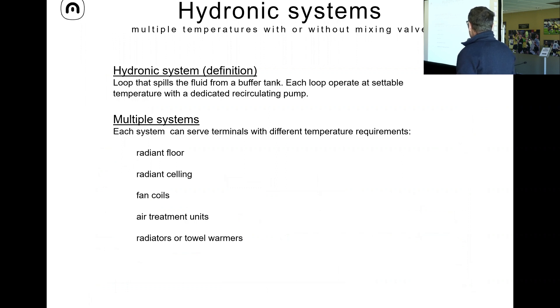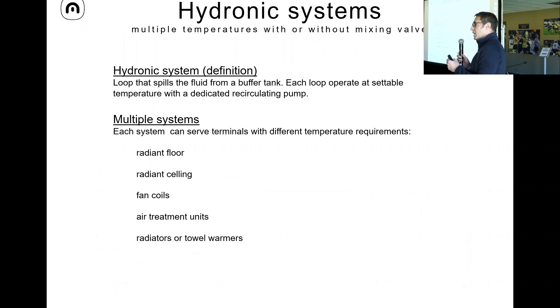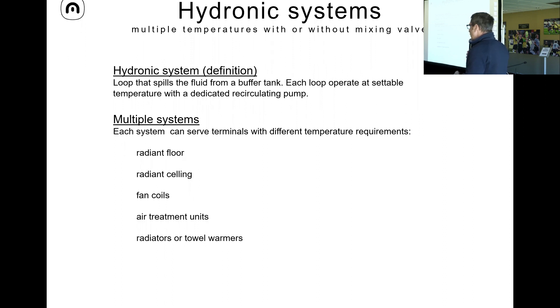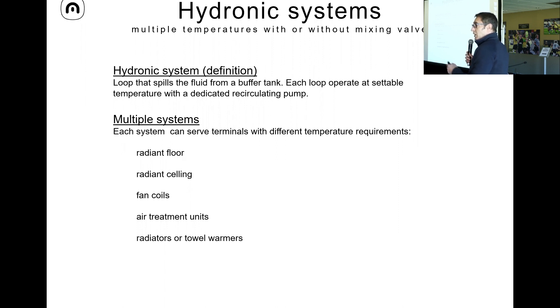One of the keys of a radiant system is the hydronic system — the hydronic loop. With the hydronic system, we mean a loop that circulates water from the buffer tank. We can handle multiple hydronic systems: a hydronic floor loop that's independent, a radiant ceiling with a modulation valve using a three-way valve to set temperature, a hydronic circuit for the fan coil supplying the coolest water, a high-temperature loop for radiators or towel warmers, and a dedicated hydronic loop for air treatment. It's a platform with a multiple hydronic system.